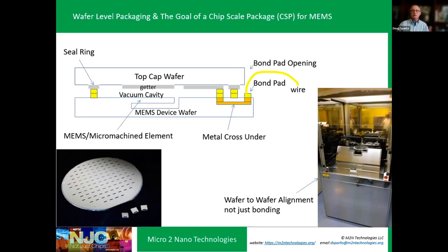You've got to have cross-unders if you're going to use wire bonding - you need to get under that seal ring and keep the seal ring hermetic. If it's a vacuum device, you've got to think about how you're bonding this in vacuum, and how the wafer surfaces are treated so they don't outgas and ruin the vacuum quality. You may incorporate a thin film getter to help improve vacuum packaging. So those are some of the wafer level and chip level design and process items you've got to contemplate when looking at packaging.